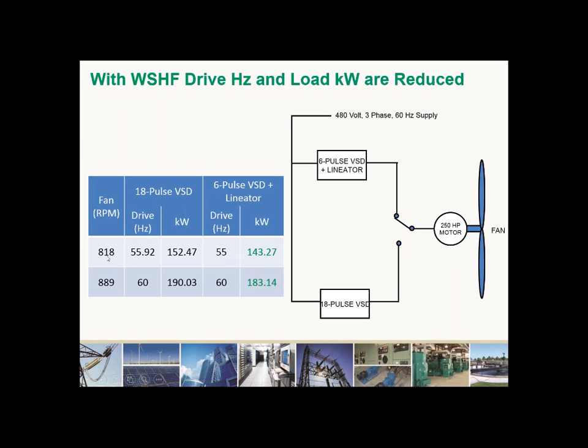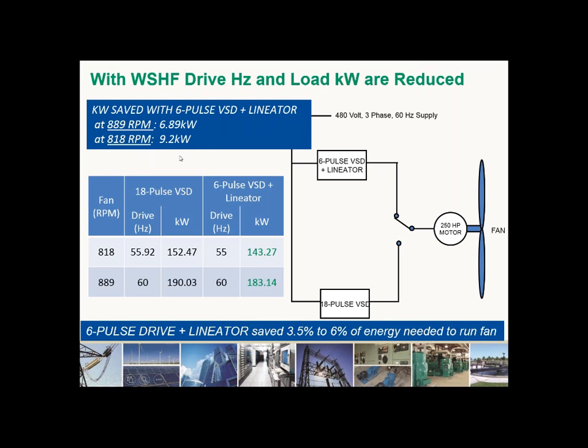When we dropped to 818 RPM, instead of requiring 56 hertz, the drive only needed to deliver 55 hertz. So it's running at a lower speed, and the power consumption dropped even further. So you not only have the reduction in the transformer losses of the 18-pulse system, we also have a reduction due to the lower speed of the variable speed drive. At full load, full speed, there was a 3.5% reduction in energy consumed. At the lower speed, there was a 6% reduction. So again, improving the voltage wave shape supplied to the drive improved the operation of the drive and lowered the power consumption even further.